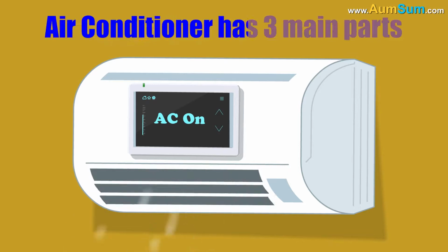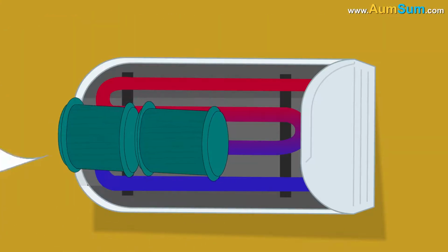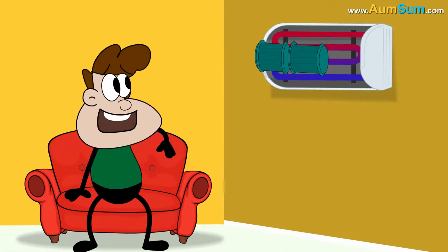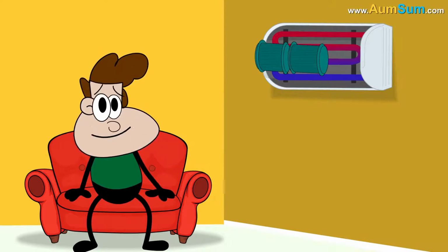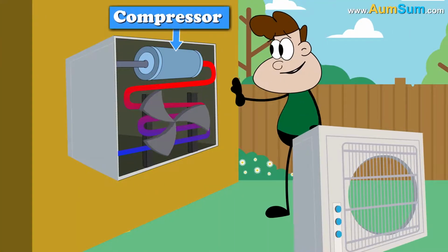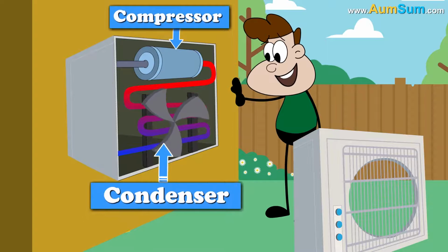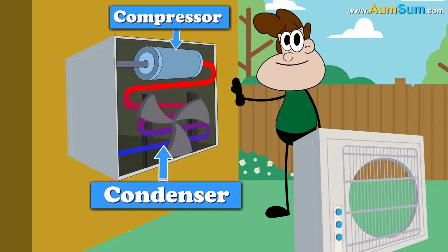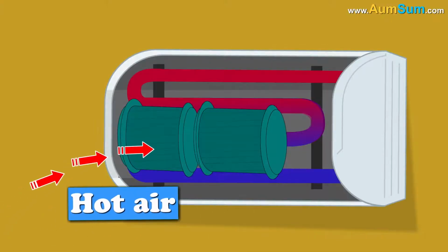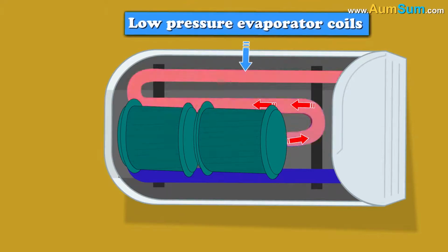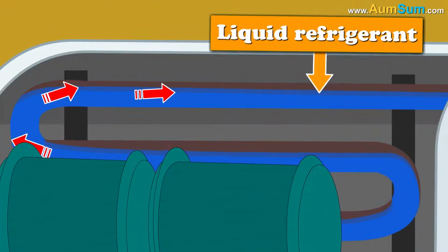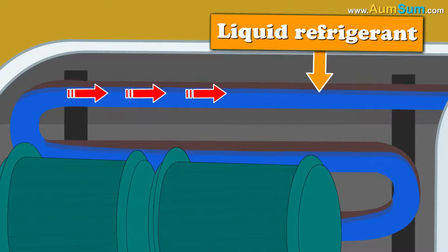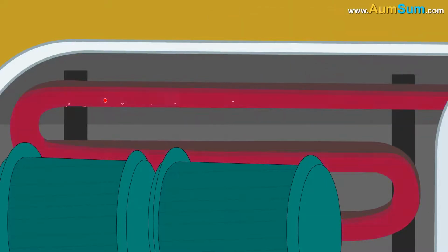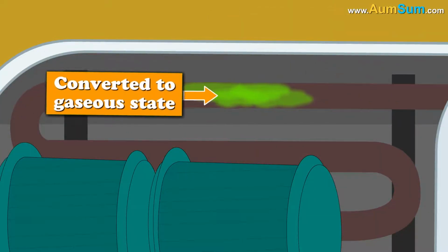An air conditioner has three main parts. Firstly, evaporator, which is located inside the house. Finally, compressor and a condenser, which are usually located outside. When hot air from the room flows over the cold, low-pressure evaporator coils, the liquid refrigerant which is present inside the coils absorbs this heat and starts getting converted to gaseous state.